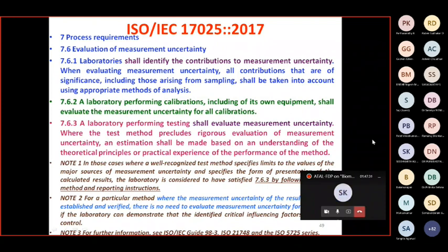Then this is another key element, measurement of uncertainty. Always remember that the standard prescribes what is the permissible measurement of uncertainty level, or the customer specifies. So you identify what are the things which can contribute to measurement of uncertainty without leaving anything out. You have to identify, then evaluate what each can contribute. If you are doing testing activity, sometimes the testing standard may not call for a rigorous evaluation of measurement of uncertainty, so it will suffice if you do some rough estimation of it. So depending upon what the standard requires, you can go for detailed measurement or just make a rough estimation.